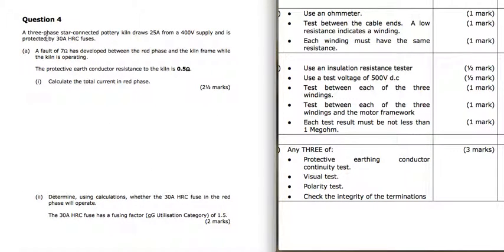Question 4, we've got a 3-phase star connected kiln that's going to draw 25 amps from a 400 volt supply, and it's protected by a 30 amp fuse. Now we've got a fault of 7 ohms within the kiln, and we've got a protective earthing conductor resistance of 0.5. So that 0.5 is less than our 1, so everything should be okay with this situation. So calculate the total current in the red phase.